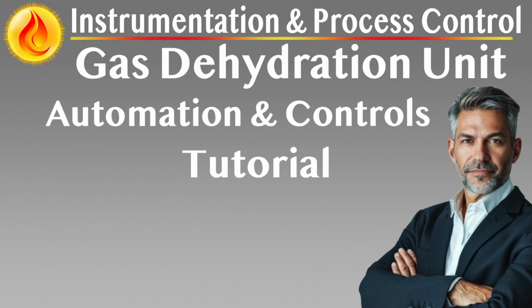Environmental and compliance integration. All instrument selections consider hazardous area certifications, Zone 2 or better, and extended temperature and corrosive atmosphere ratings, e.g. H2S exposure. Minimal emissions from flash and still overheads are monitored by gas recovery or flare system instrumentation. Summary. The instrumentation and control systems of glycol gas dryers are designed to deliver exacting control over critical process variables while ensuring safety and environmental compliance. With high-fidelity sensors, responsive control elements, and protective interlocks, these systems uphold operational integrity across a range of operating scenarios, from startup and turndown to full load conditions.